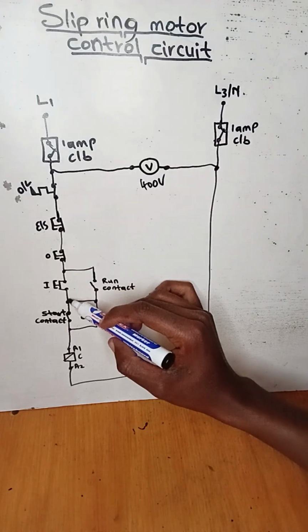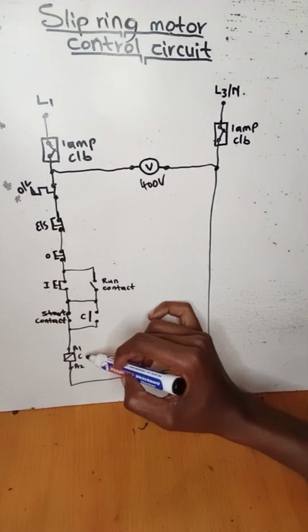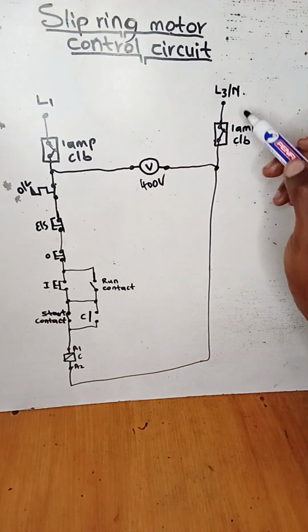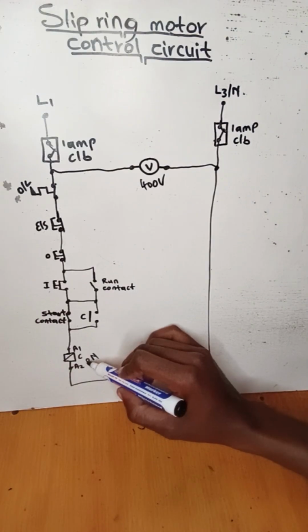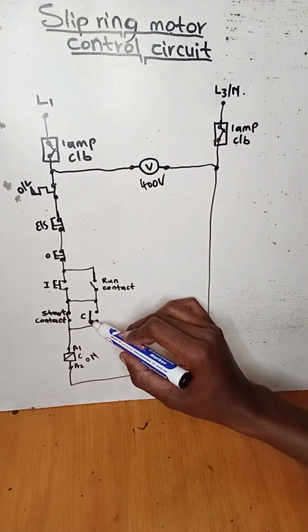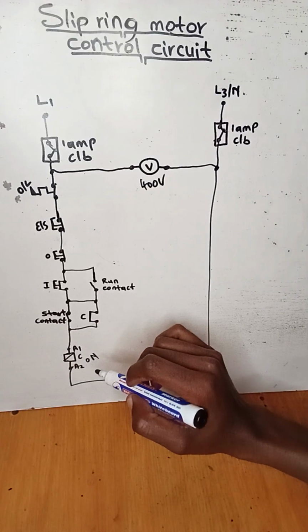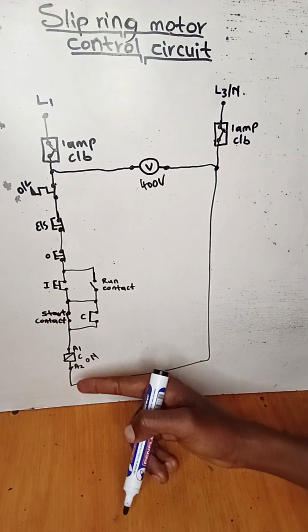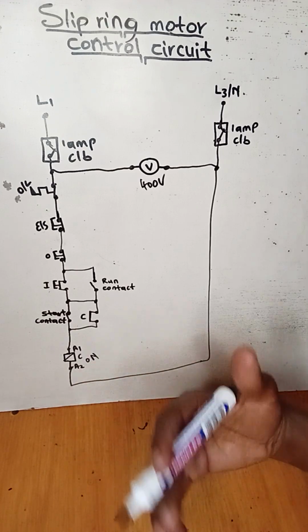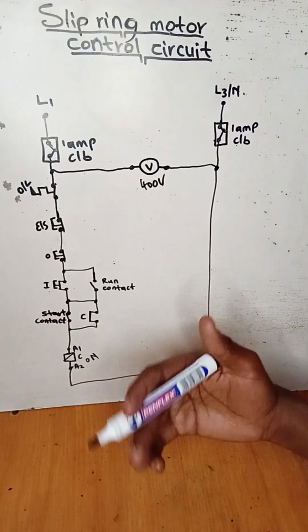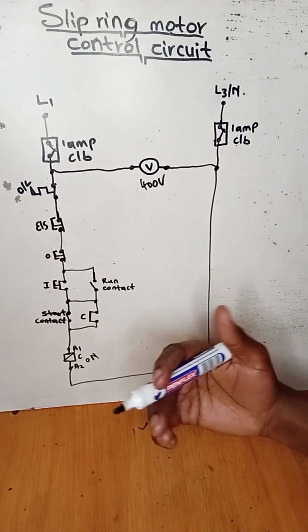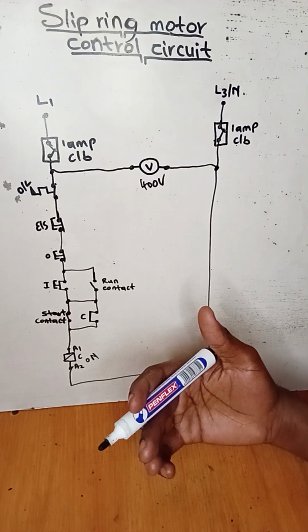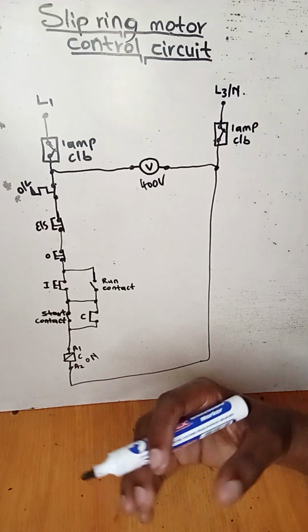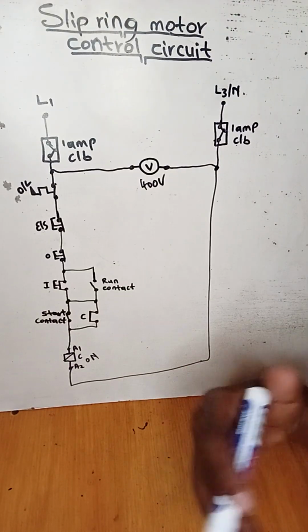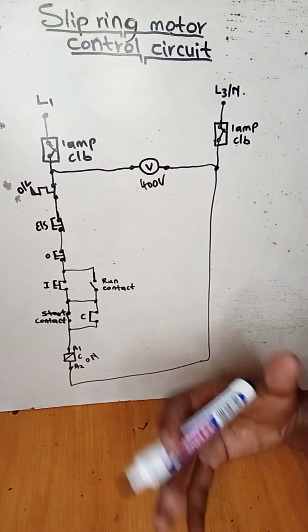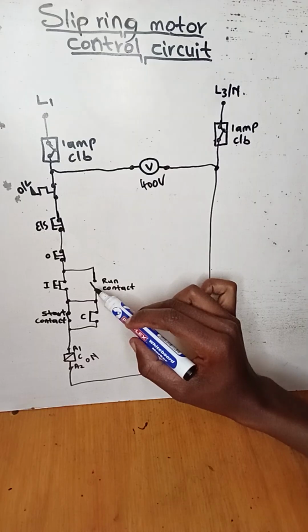So when we press that button, current will flow all the way to A1 of the coil of the contactor, and A2 gets live 3, which means the coil of the contactor will be on. When it's on, it will affect these contacts. It will be closed here, and then since our coil is energized, when it keeps on being energized, that's when it affects the run contact to be closed. It triggers the run contact when the motor keeps on running, right?